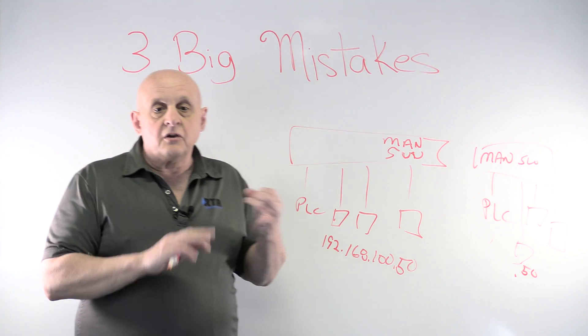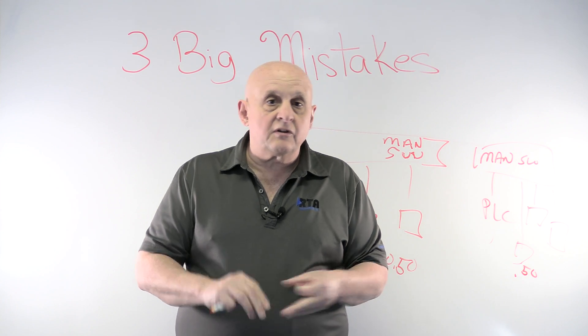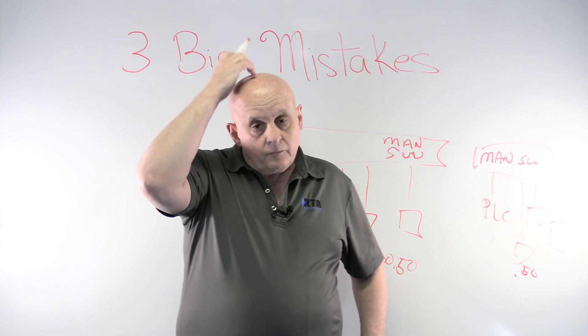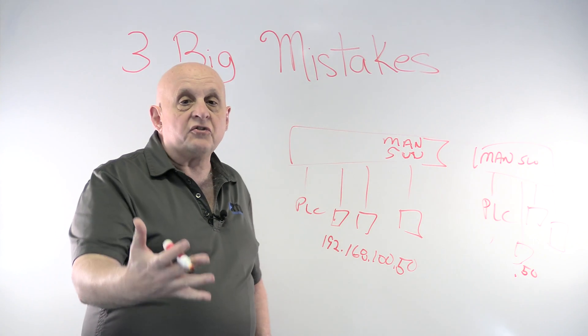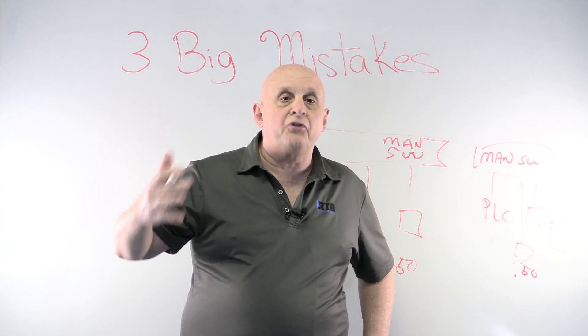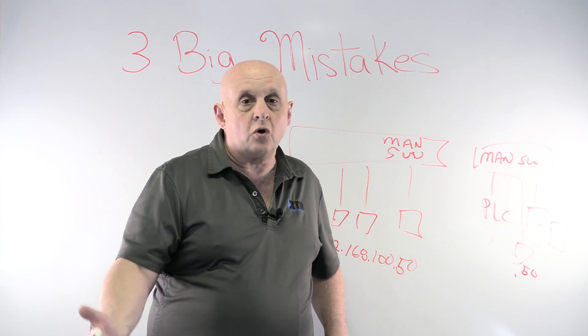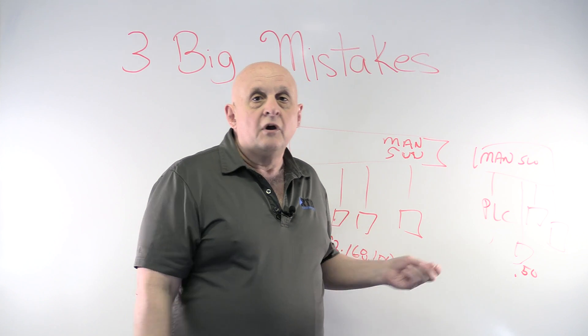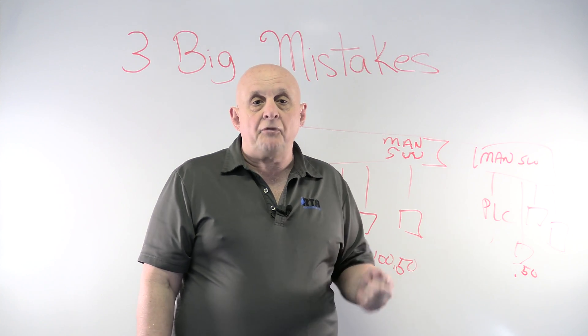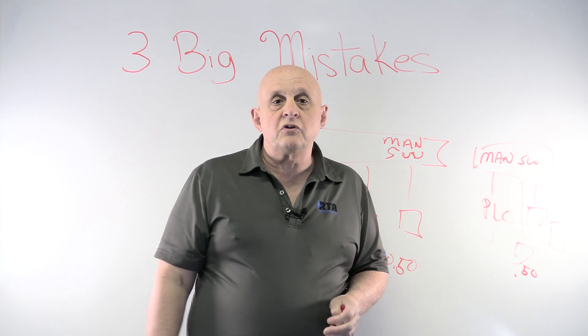So those are the three things: control messages get priority, use full duplex and switched networks, and architect your system so that every PLC has a managed switch. These are some of the recommendations in the new book that Gary Workman and I wrote. Gary Workman has 30 years of experience putting Ethernet IP networks together. The book will explain all 12 recommendations for building Ethernet IP control systems — there'll be a link below where you can get on the list to receive it.